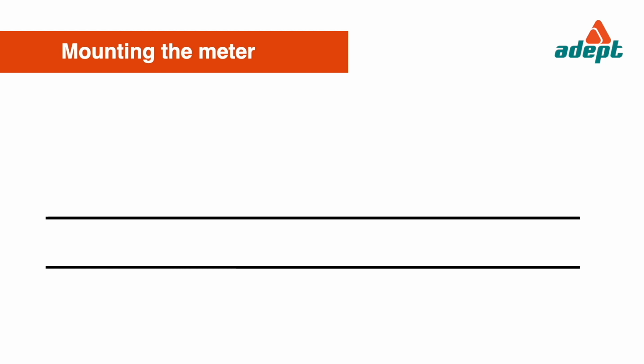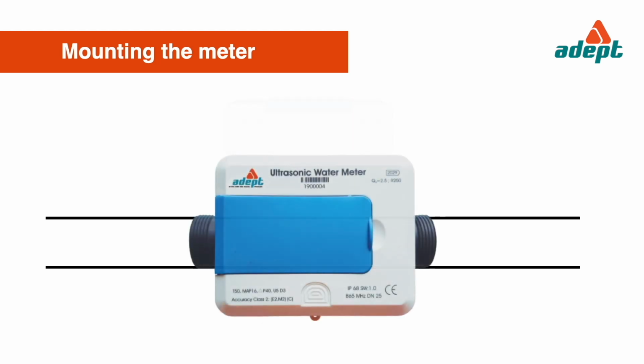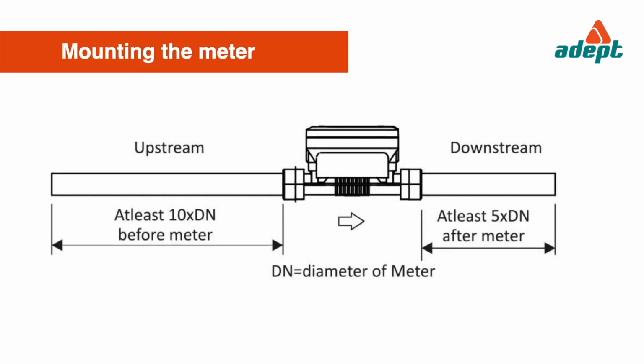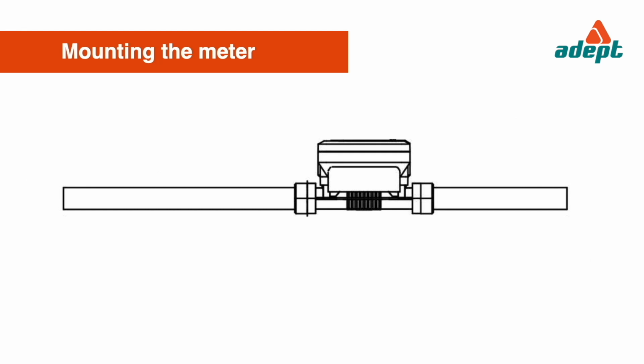Mounting the meter. Consider the dimensions of the water meter and its distance from the surroundings. Straight sections of 10 times DN before and 5 times DN after the meter are recommended to streamline the flow of water. The meter is to be installed so that the direction of the arrow on the meter housing corresponds to the direction of flow.